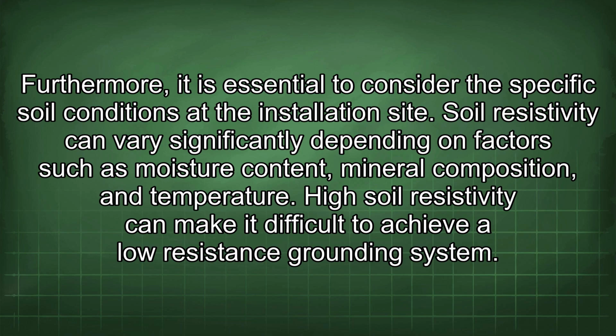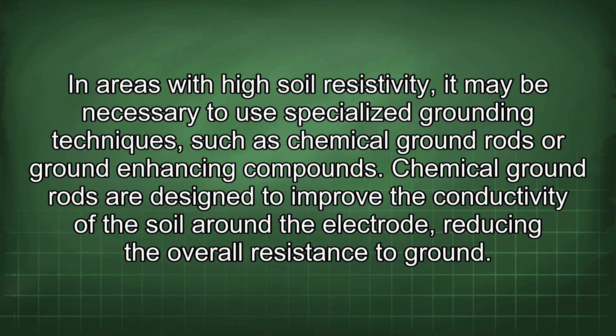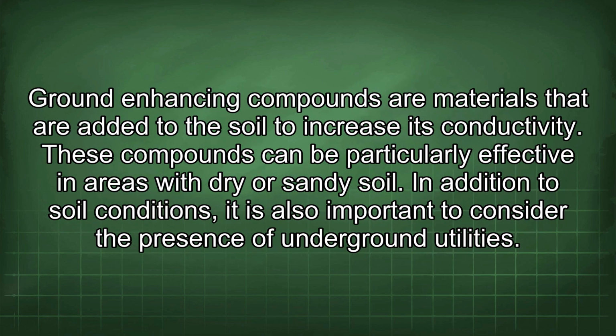High soil resistivity can make it difficult to achieve a low-resistance grounding system. In areas with high soil resistivity, it may be necessary to use specialized grounding techniques, such as chemical ground rods or ground-enhancing compounds. Chemical ground rods are designed to improve the conductivity of the soil around the electrode, reducing the overall resistance to ground. Ground-enhancing compounds are materials that are added to the soil to increase its conductivity. These compounds can be particularly effective in areas with dry or sandy soil.